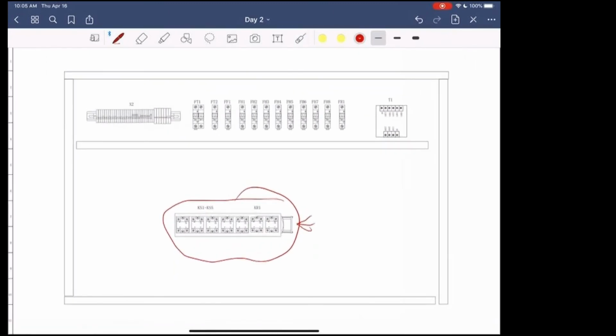And usually when the SSRs burn out, they burn out in a normally closed condition, which means that you'll always have power going to your heater bands, and your heater band will override and therefore cause overheat and burning of your material.